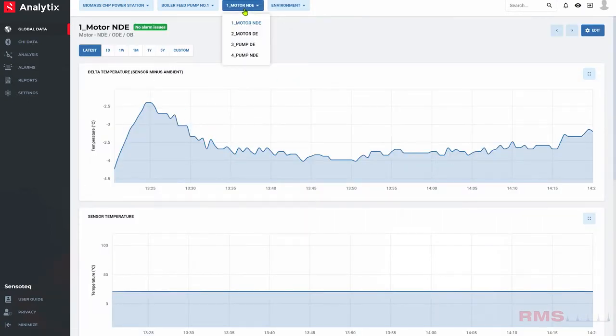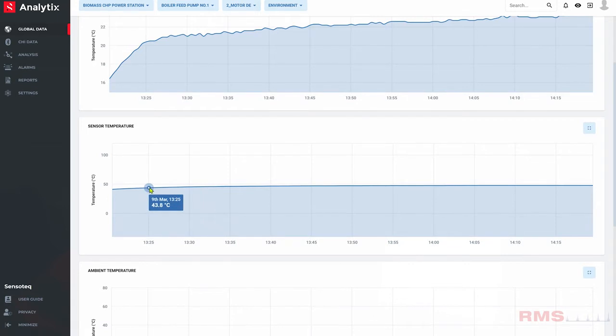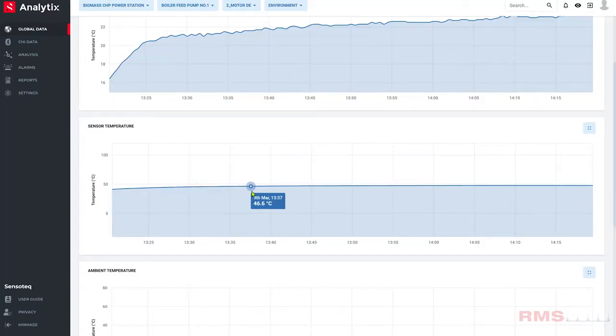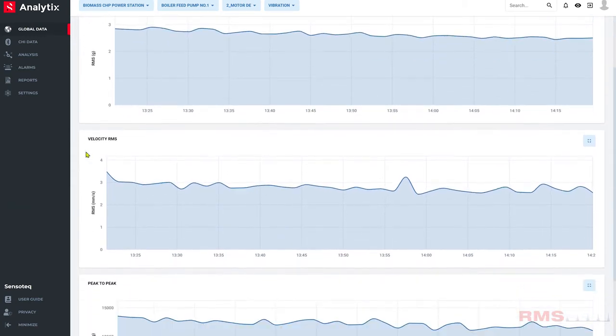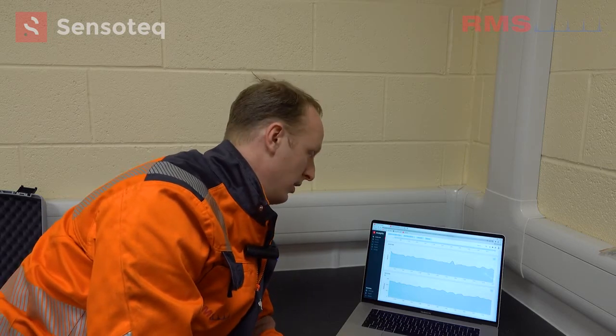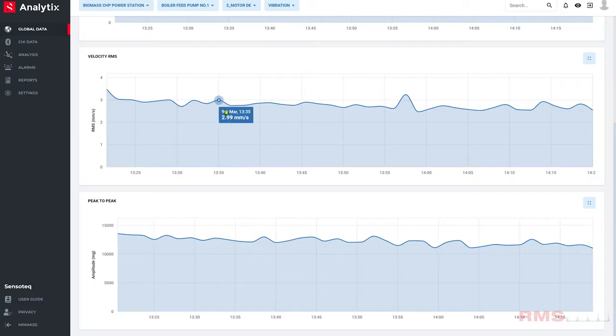The way this system works is we get a measurement from the sensor each minute, and then every 12 hours we get a full spectrum in the long interval data. Looking at the environment tab on the motor drive end — it's a bit warmer at that bearing — you can see it's warmed up with incremental data. Each minute brings a different data point: it could be temperature, vibration overall velocity overall, or acceleration peak-to-peak G's. Moving on to vibration, I've got acceleration RMS overall, velocity RMS overall, and peak-to-peak in G's — giving us the trending measurement we want.